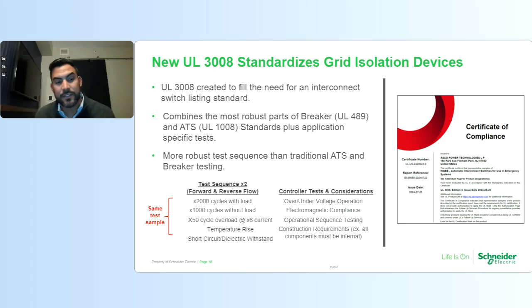So it's tested 2,000 times with load. When you detect the utility outage, the breaker opens, closes back, that's one cycle. 1,000 times without load. Again, this is a bidirectional device. 50x the cycle overload rating, temperature rise test, withstand and close-on ratings. With all that testing criteria and robustness, you would want an interconnection switch to ensure that if you're going to use that energy storage system for an emergency system, you have a device that's specifically tested that can enable that energy storage system to come online with some type of UL standard. Additionally, we tested the controller as well, which allows for that grid interconnection mode with the primary source, to detect a utility outage and then disconnect from the primary source to enable this microgrid to operate in island mode. So it's a UL certification. You can see there on the right. Any questions, please post them in the chat.